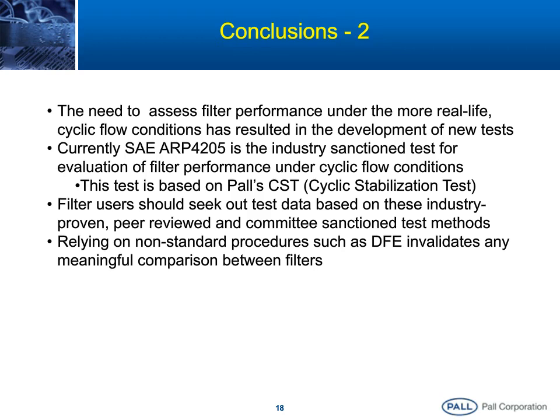Filters play an important role in the service life and reliability of hydraulic and lubricated machinery. It is therefore important to rely only on filters that are rated by industry-sanctioned standard test methods and not by non-standard tests. Using the nominal rating of a filter without any details about the test method or relying on non-standard tests such as the DFE test invalidates any meaningful comparison between filters.